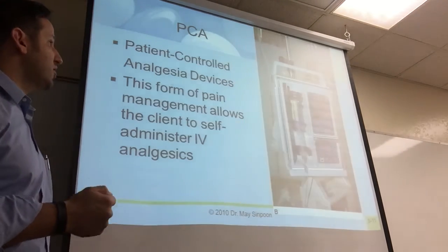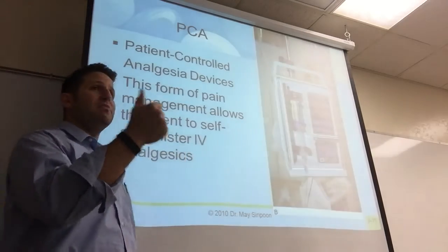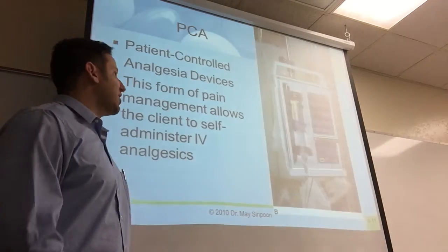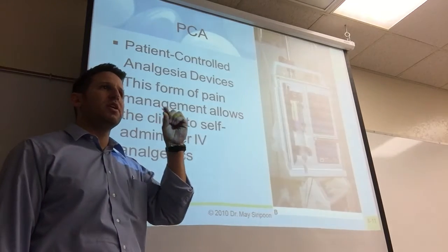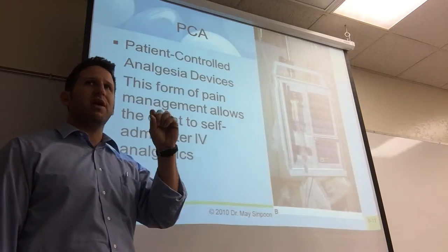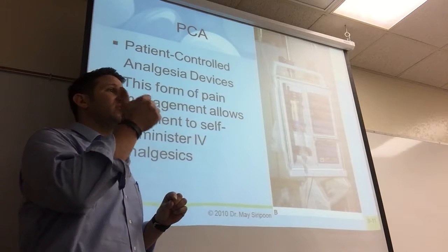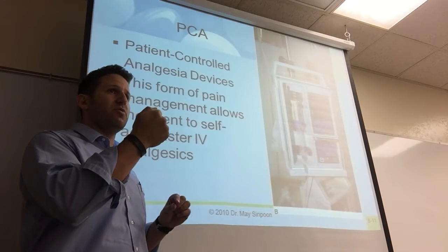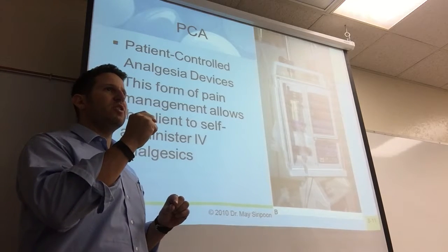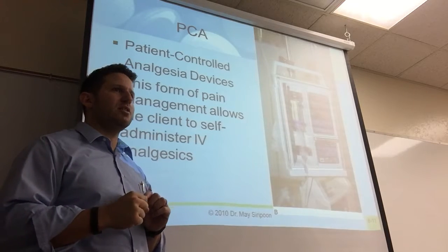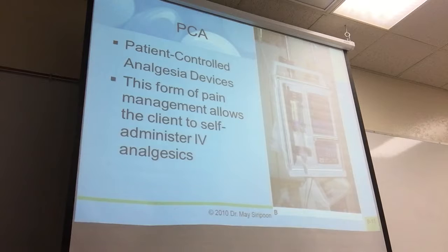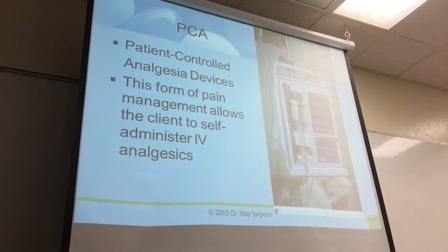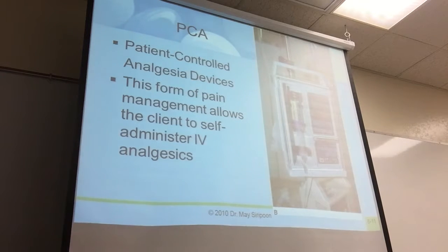The other thing it does is not just a one-time dose every time they push the button. There's also a continuous rate you can program in, so they get a tiny low dose that runs continuously to help manage pain. Then you can set the bolus dose from the button at a lower dose, so you're using less narcotics and they have better pain management. It's commonly used for surgery cases, and then you can wean them off the PCA and put them on oral medications, and they do quite well.